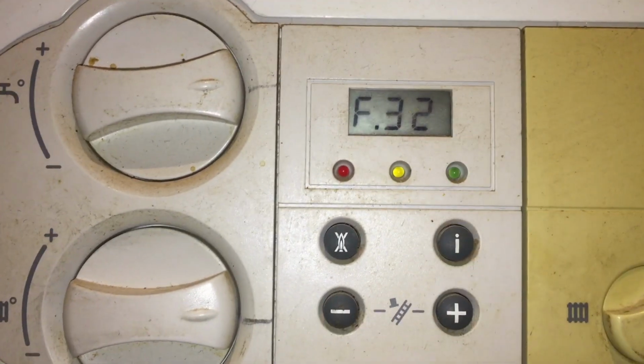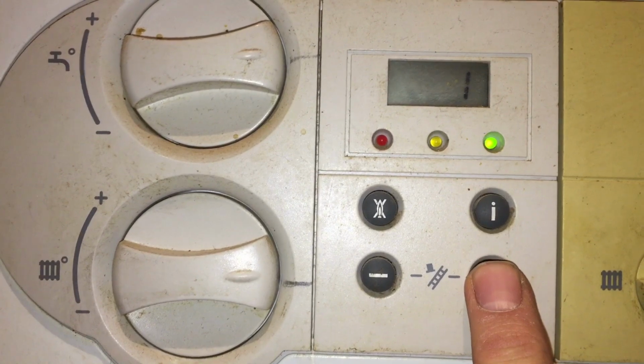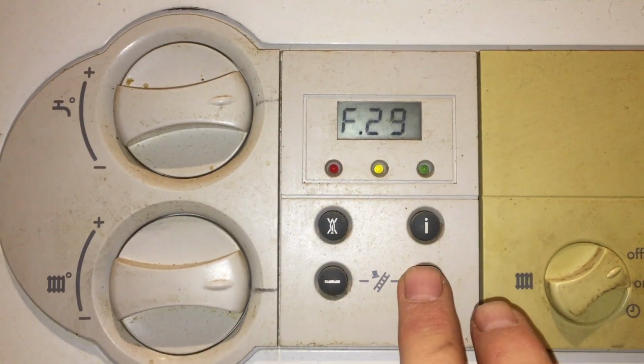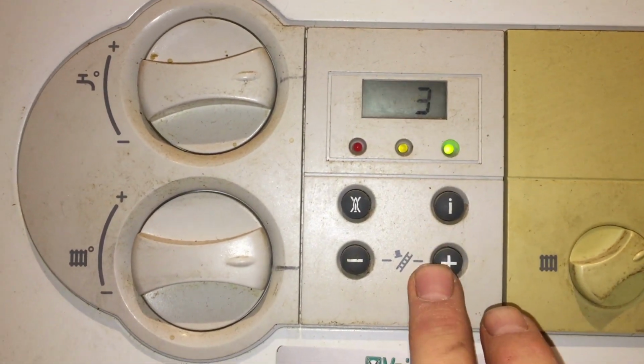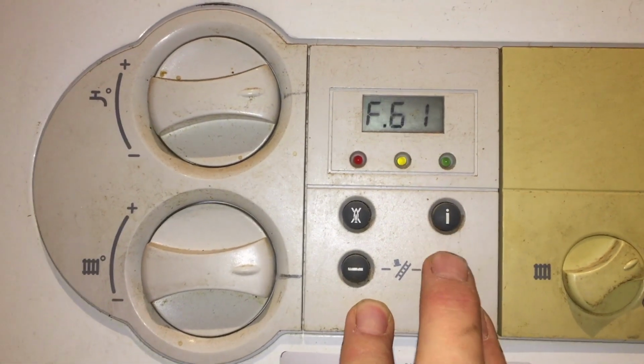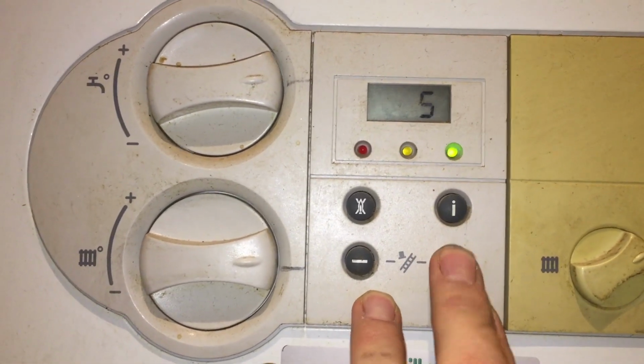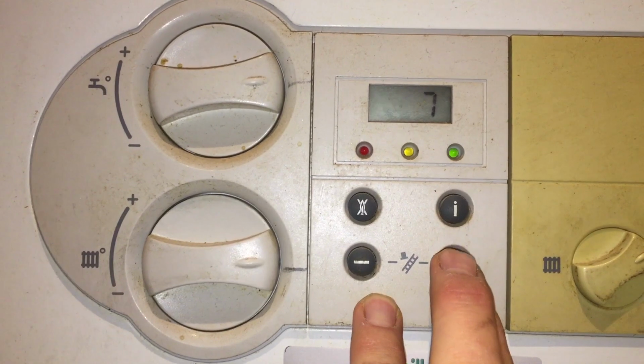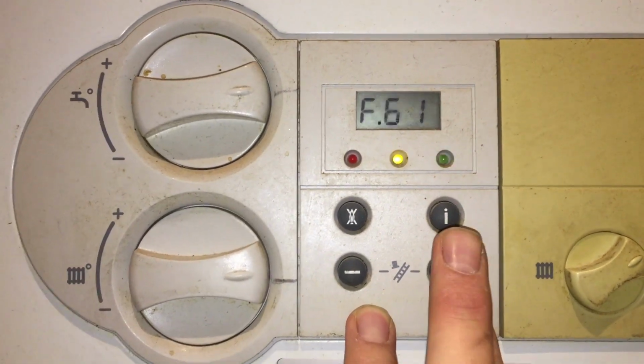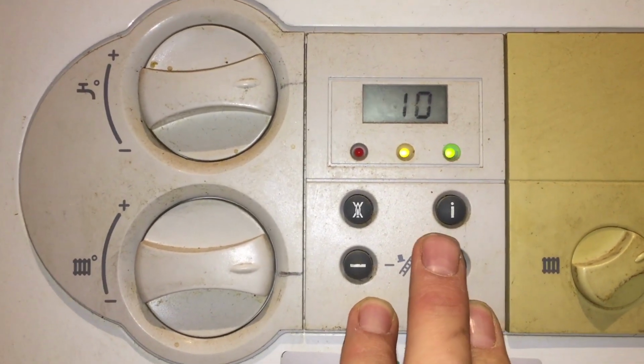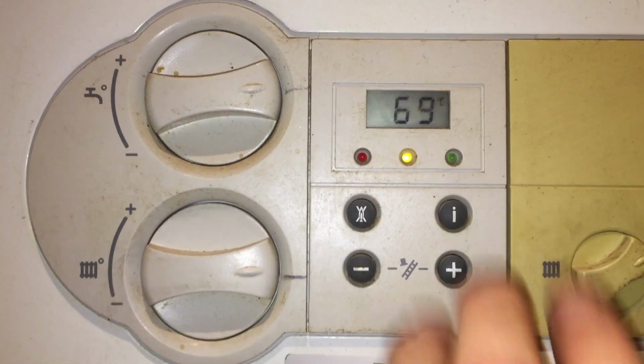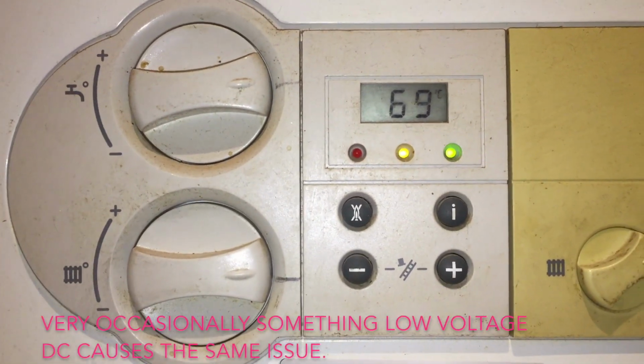We're going to the fault history, and so basically I've done a service. The woman complained that there was an intermittent fault. You go in the fault history, and here we go. F61, F61, all F61s. When I first checked, when I arrived, all 10 were F61, which, in my experience, has always been the PCB.